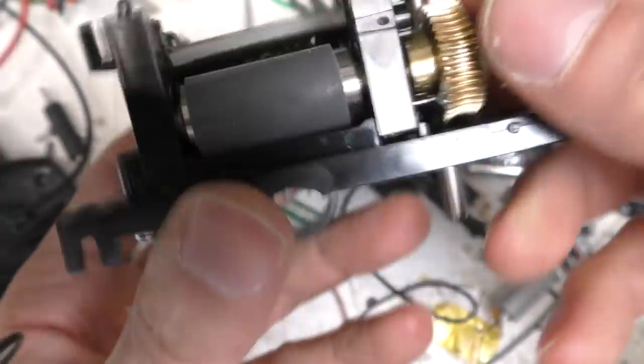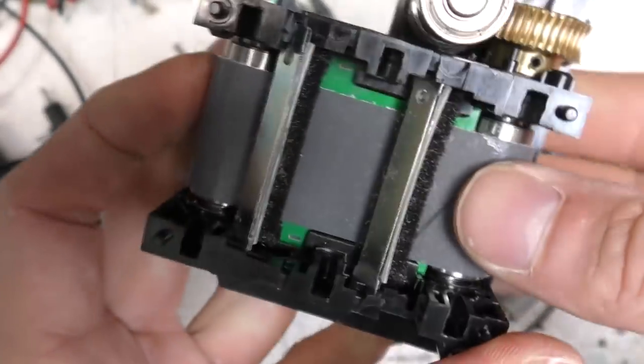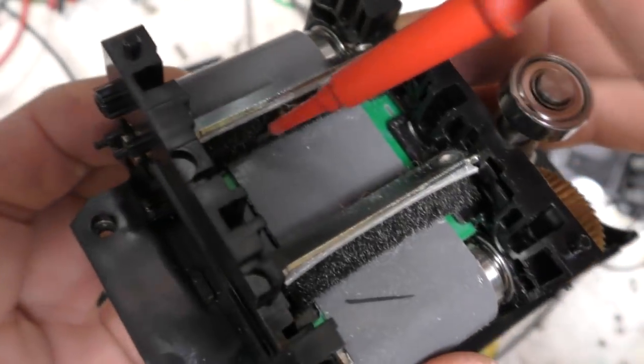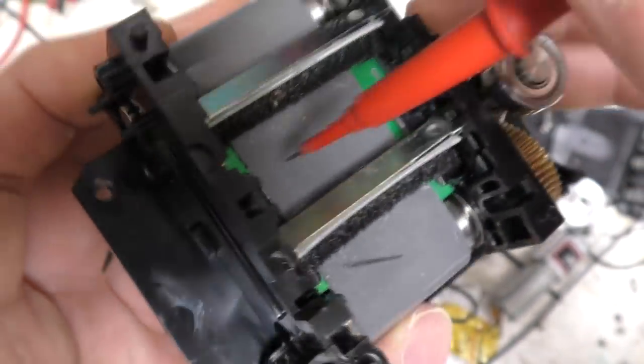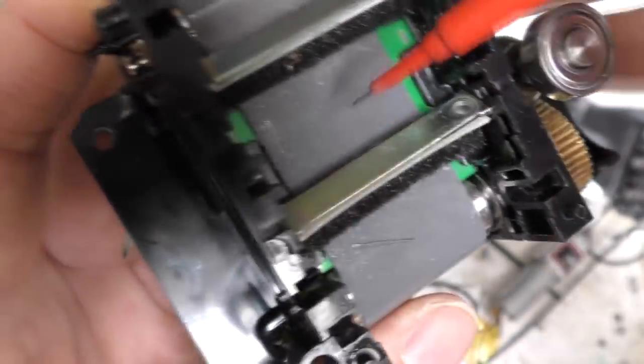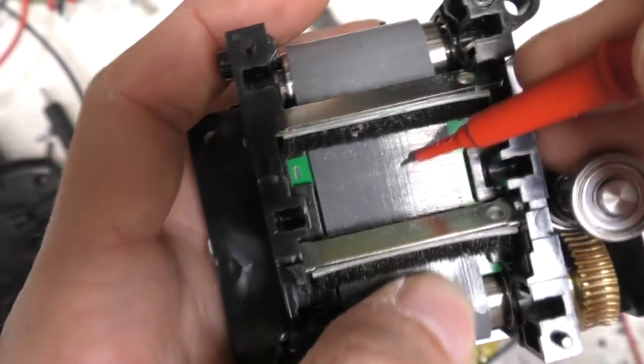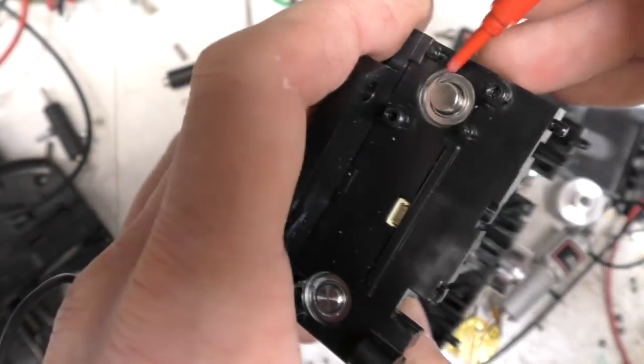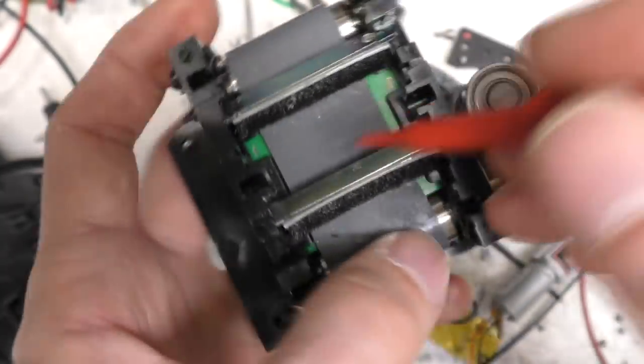And looking closer at this, it looks like the plate is actually carried on this sort of grey, rubbery type belt material. And there's also these black brushes, which are obviously to keep the light out, because that photo multiplier is very sensitive, so you need to keep all the extraneous light out of the sensing area. And so it's driven from that end, and then the encoder is on the other end, so that any slop in the belt is compensated for. So it's using the actual output from the encoder to time the scanning. And the belt runs over these cylinders, which have got nice ball races. Again, this is super high quality mechanics.